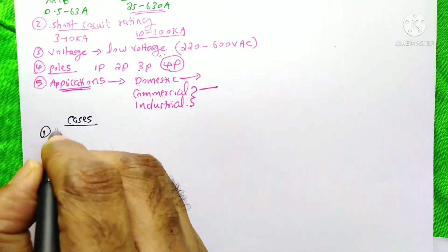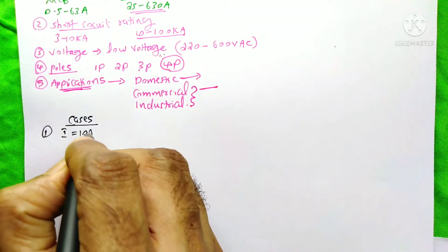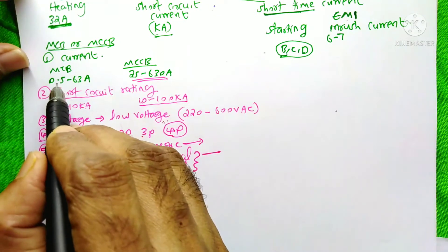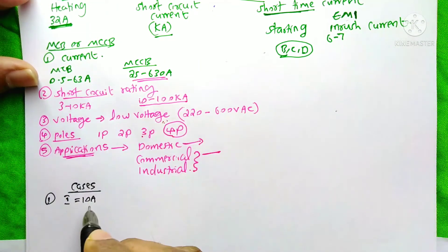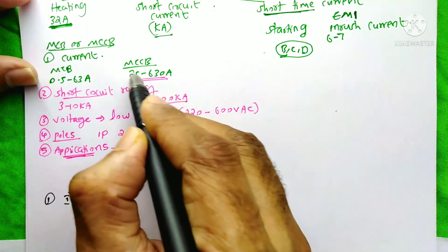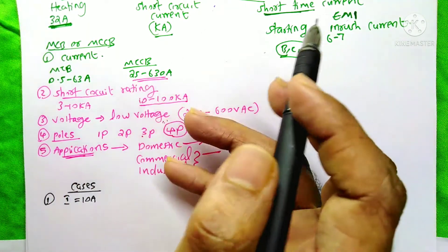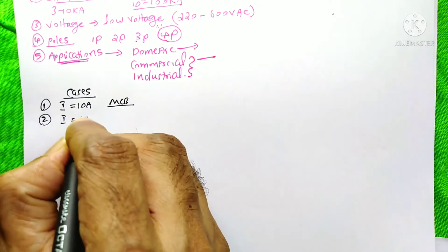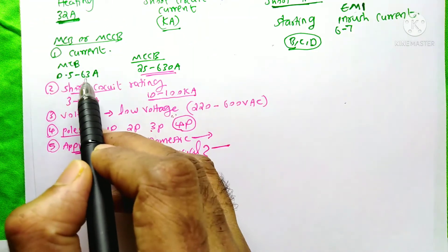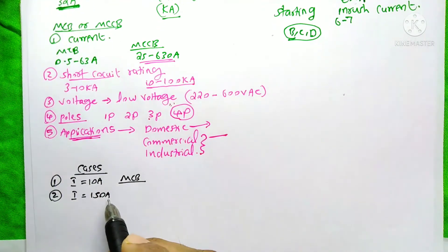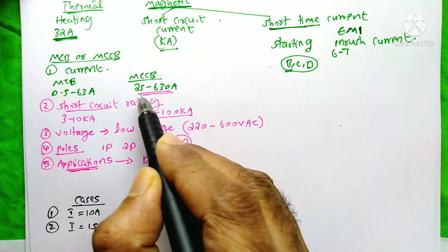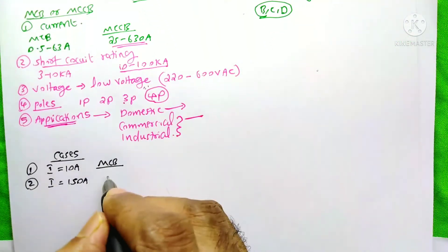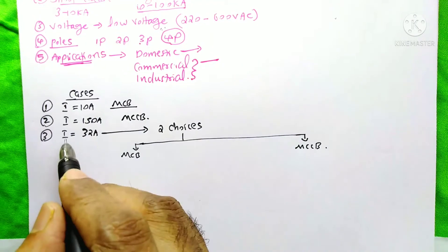Let's discuss some different cases. If the circuit current is 10 amperes: the MCB is available from 0.5 to 63 amps, so 10 amperes falls within that range, but there is no 10-ampere MCCB available — so we are forced to select an MCB. The second case is when the current is 150 amperes: the MCB is only available up to 63 amps, but 150 amperes falls within the MCCB range of 25 to 630 amps, so we are forced to select an MCCB.